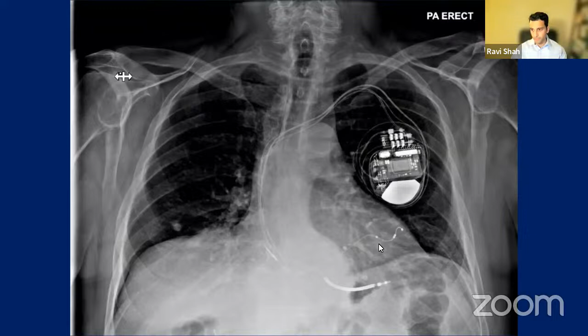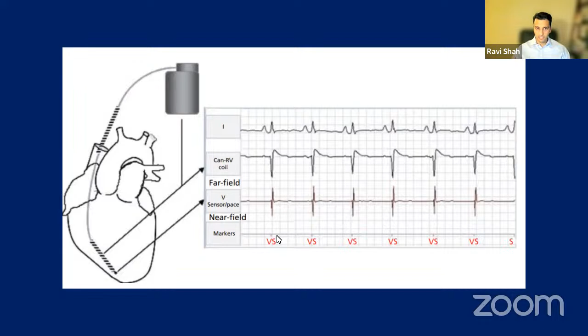When we look at the device interrogations, this is just a schematic of what we see. And so, again, you have your generator and 1 or 2 coils. It's standard of practice now to only implant single coil devices. And so what we see is a CAN to RV coil, so a vector from the coil to the CAN, and then from the tip to the CAN, which represents the pacing vector. And then what you'll see on the bottom or the top is how the device is characterizing the signals that it sees.